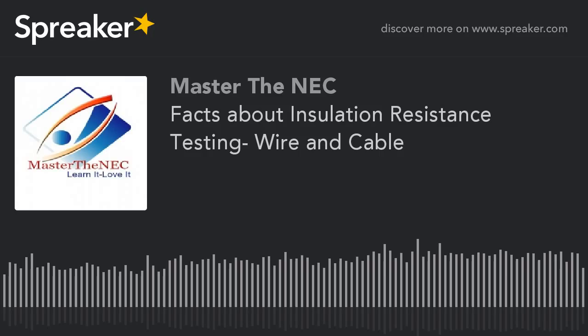Now, that's a perfect condition in a perfect world. Now, when you're out in the field, it's not so easy, because if I have two insulated conductors and I'm trying to hook between the two, which is routinely what's talked about in a lot of these training manuals, they say test A to B, B to C, A to C, and then each individual conductor to ground. It even talks about isolating. If you're testing A, connect B and C also to the equipment ground, and do your testing to isolate out.